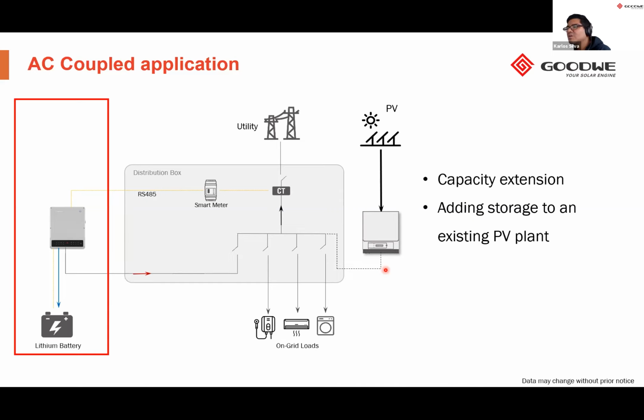So one of the major rules is that if you significantly modify that grid-connected PV plant, then you lose your tariff. So a lot of people are leaving their PV plants, receiving the feed-in tariff from these PV plants for the next 10 to 20 years, and then they're adding a battery inverter to add storage capability to that existing power plant. So a battery inverter is very good for retrofit solutions to existing PV plants.